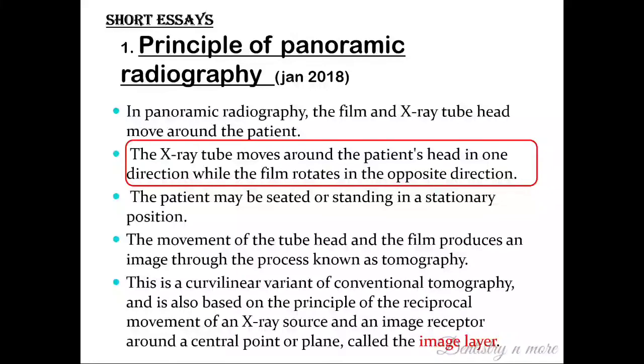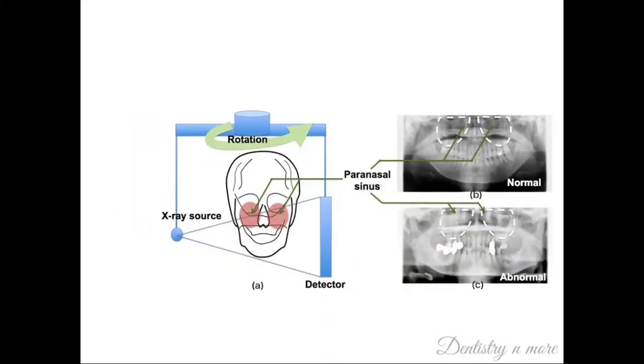In the diagram, there is a center of rotation where the patient's head is stationary. The x-ray tube head moves around one side of the patient and the receptor assembly moves towards the opposite side. The image receptor slides past the collimator sequentially, producing a latent image. There is a charge-coupled device image receptor wherein a vertical charge-coupled linear array behind the collimator continuously reads out the exposure to produce an image.